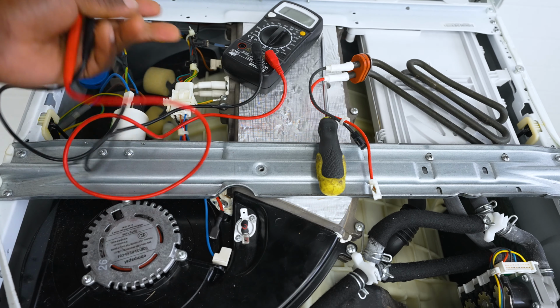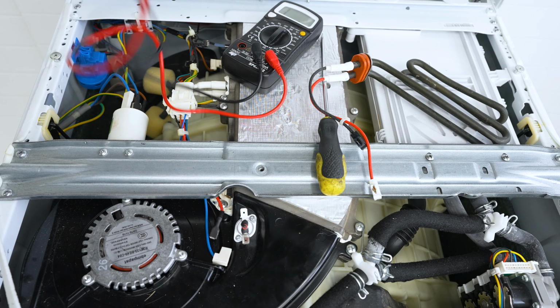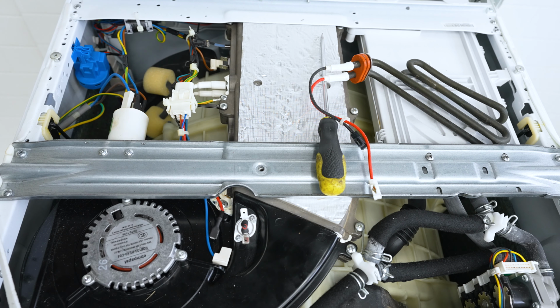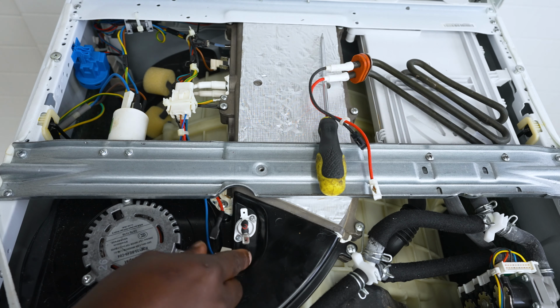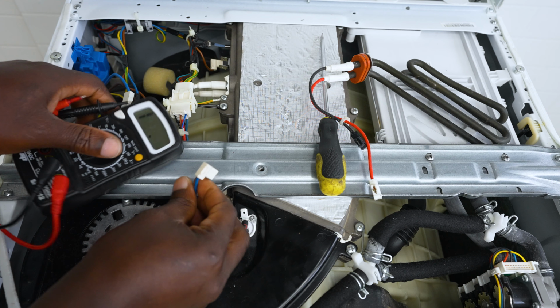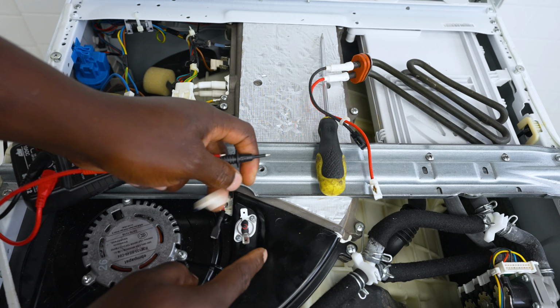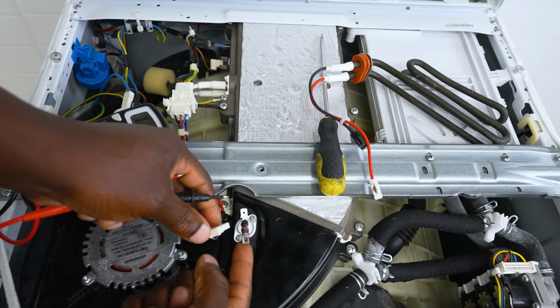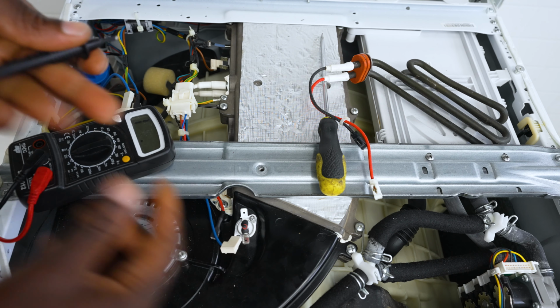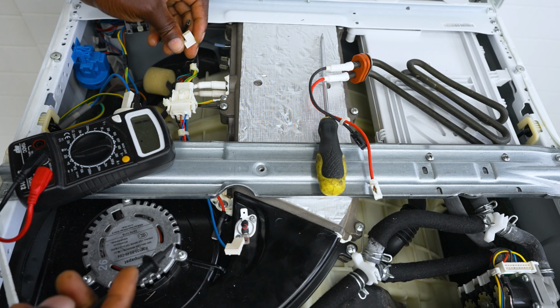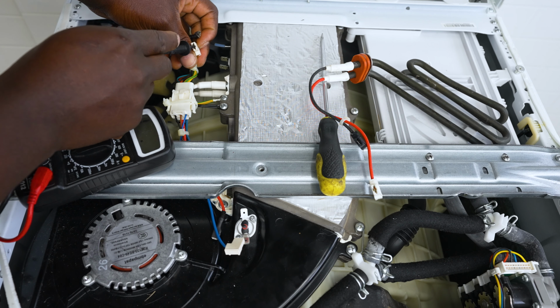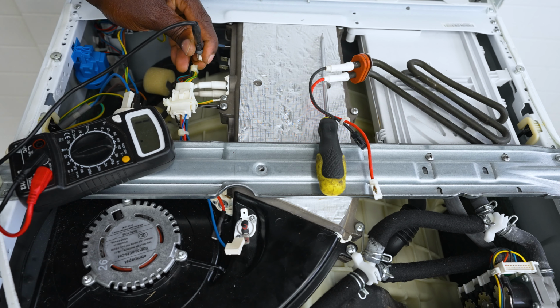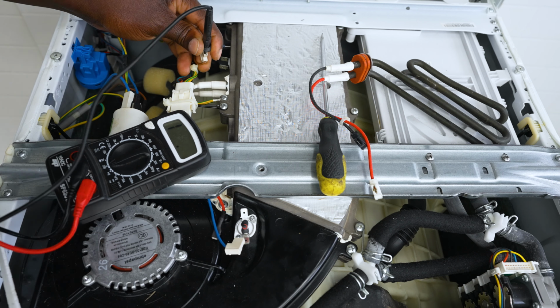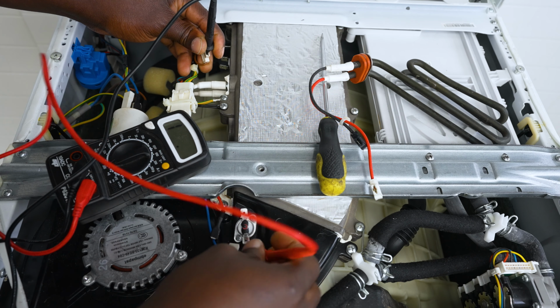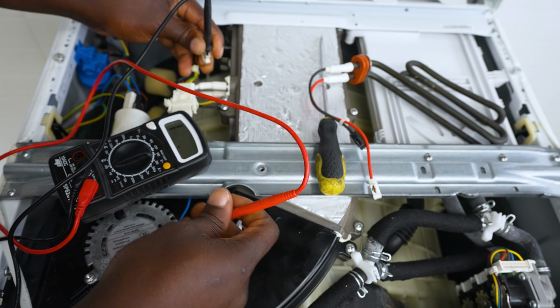Another thing you can do, if you've tested your heating element and seen it's working and want to find out further where the problem lies, you'll see there's a blue wire connected to this resettable thermostat, and a brown wire. So you've got your live and your neutral there. Just connect one probe to one and the other probe to the neutral.